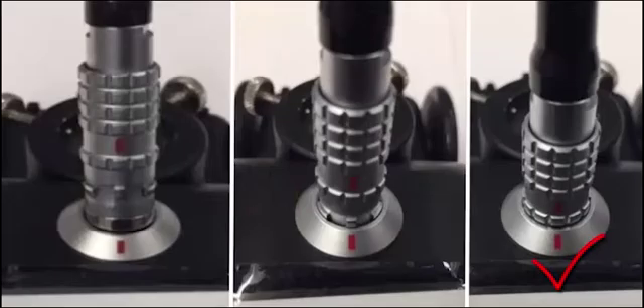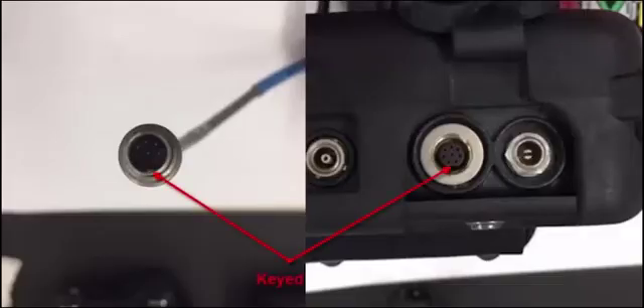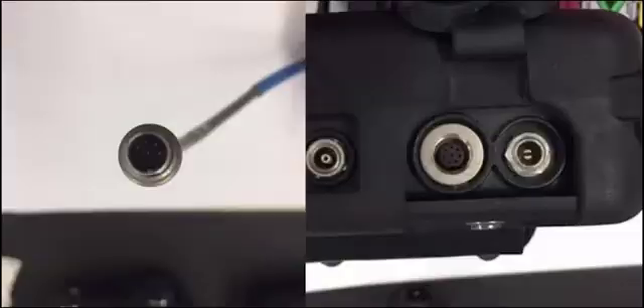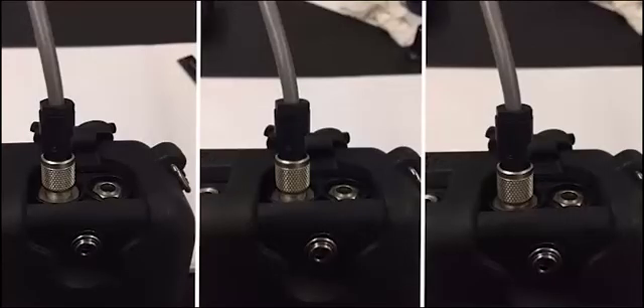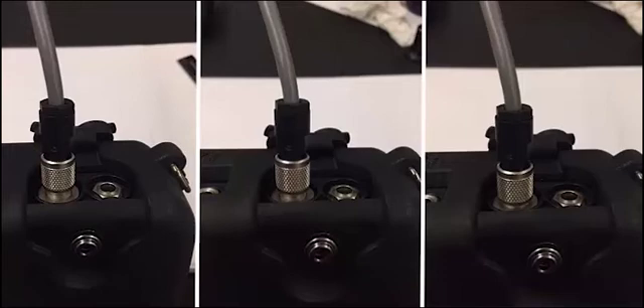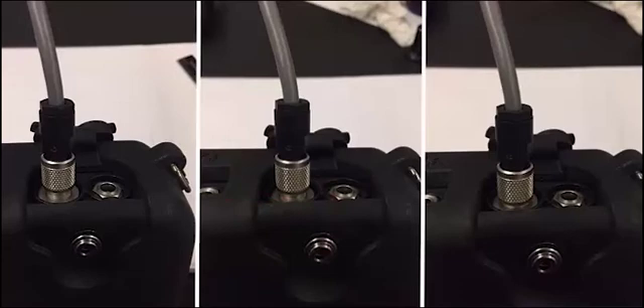We can now plug the other end of the encoder cable into the top of the 38DL Plus. These connectors are also keyed, but they do not contain red markers. Pay close attention when connecting the encoder cable to the top of the 38DL Plus. Make sure that the keyed section of the encoder cable is properly seated in the slot of the port on the top of the 38DL Plus. Once it is seated properly, you can screw in the cable by applying slight pressure and turning the knurled section of the encoder cable clockwise. Screw in the cable until it is snug. It does not screw in all the way, so some threads will likely be exposed. This is fine.